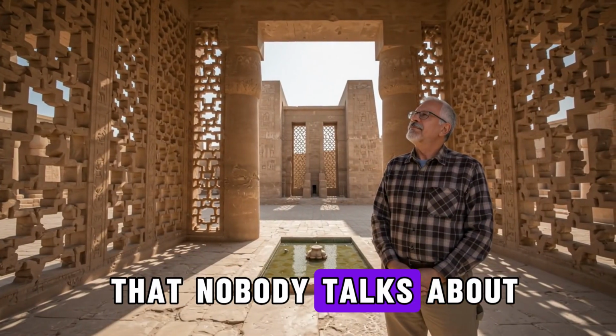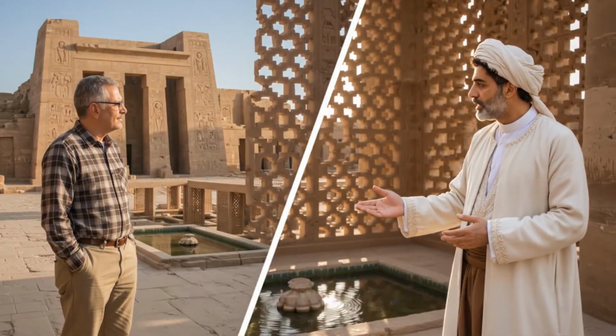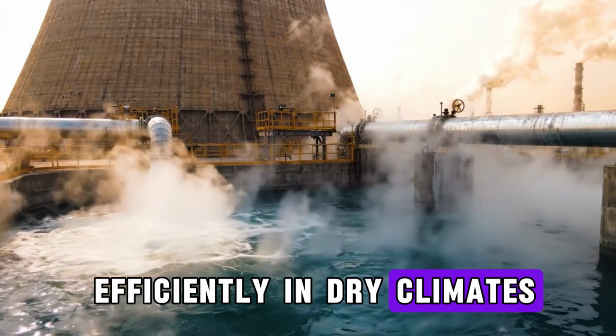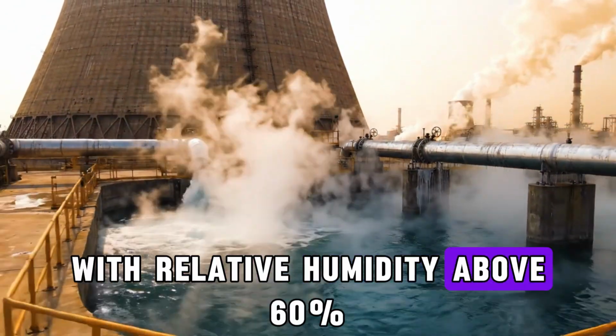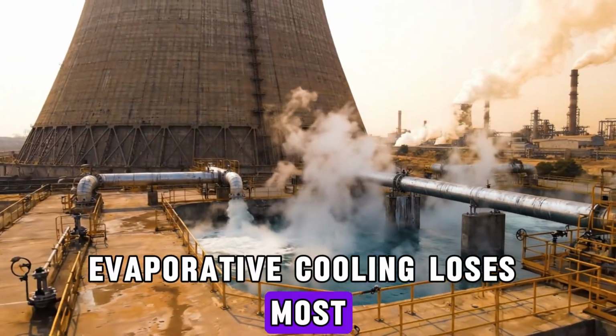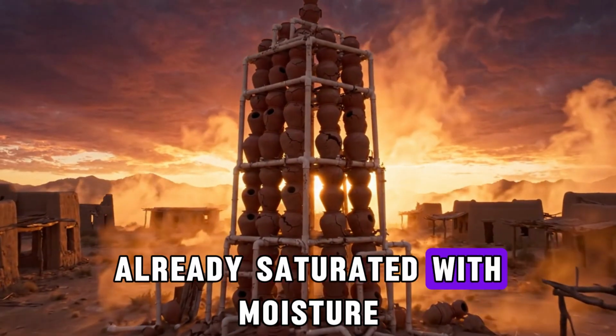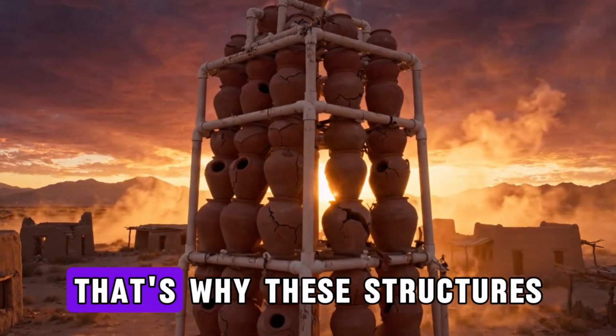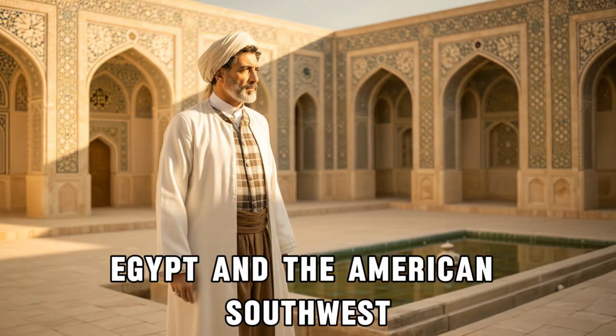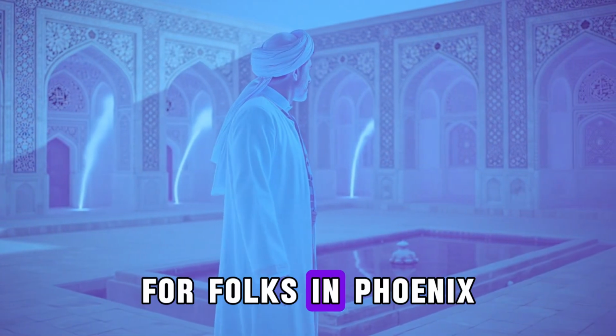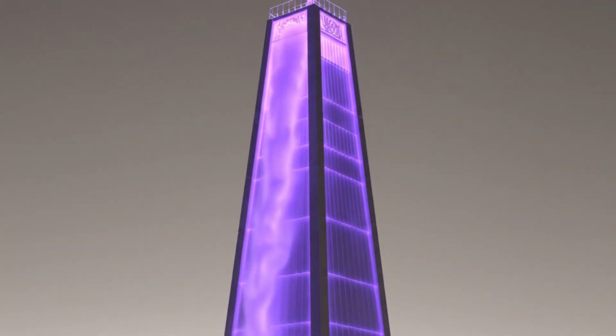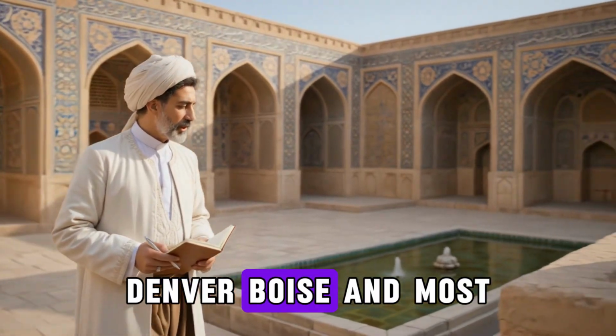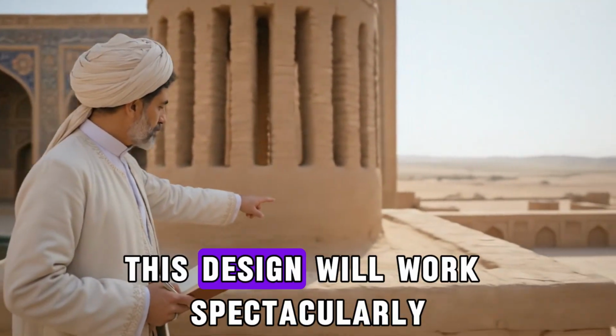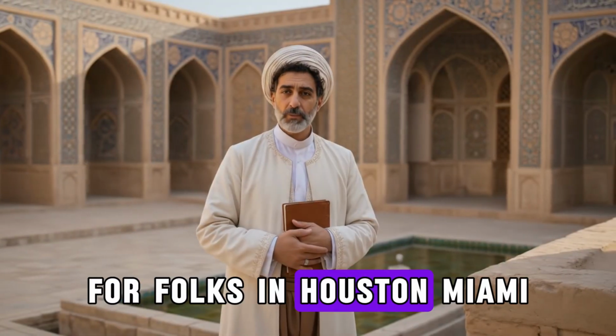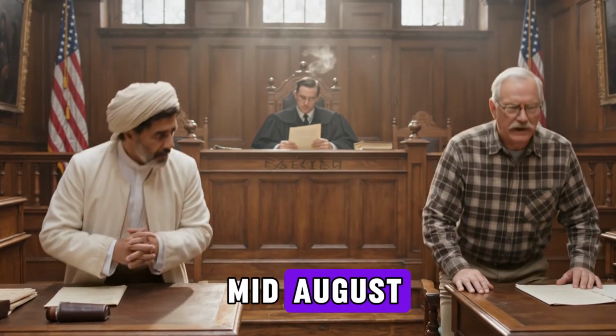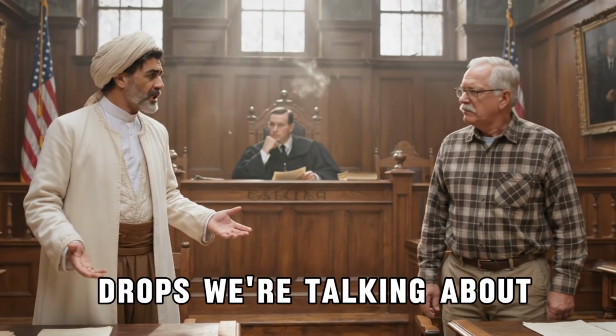But here's the catch that nobody talks about, and this is where the design gets serious. These towers only work efficiently in dry climates. If you live somewhere with relative humidity above 60%, evaporative cooling loses most of its effectiveness because the air is already saturated with moisture and can't absorb much more. That's why these structures originated in Persia, Egypt, and the American Southwest. For folks in Phoenix, Albuquerque, Las Vegas, El Paso, Reno, Denver, Boise, and most of inland California, this design will work spectacularly. For folks in Houston, Miami, New Orleans, or Atlanta in mid-August, you'll get some cooling but not the dramatic drops we're talking about.